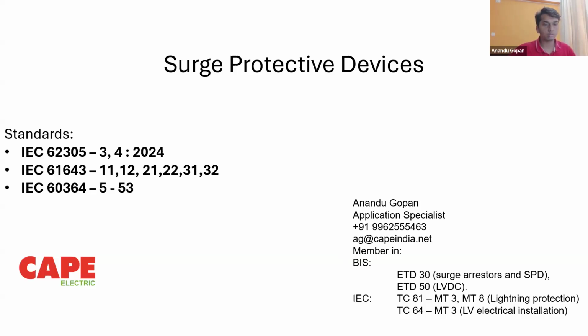I'll be explaining about surge protective devices, and on the left side of my slide you can see the standards related to surge protective devices. The first one is IEC 62305, parts 3 and 4. IEC 62305 talks about lightning protection; in part 3 you will find SPDs in equipotential bonding, and in part 4 you can find protection for internal systems. IEC 61643 is the main SPD standard. In this you can find 11, 12, 21, 22, 31, 32. In the future you can also find 41, 42.